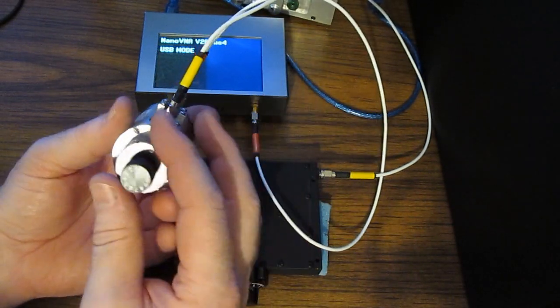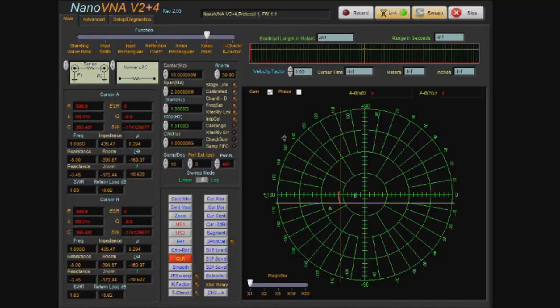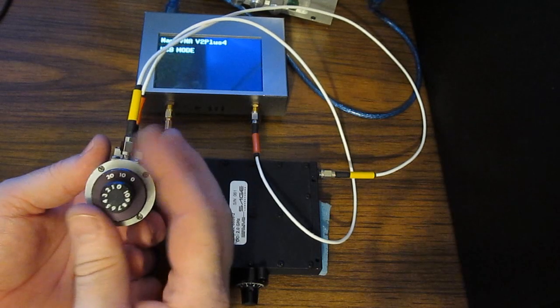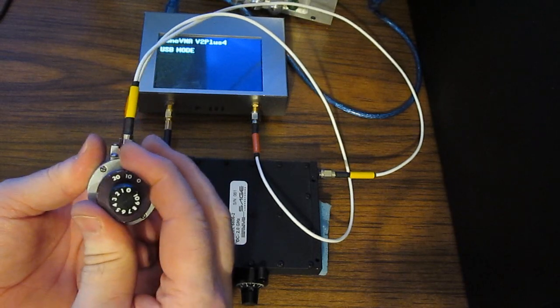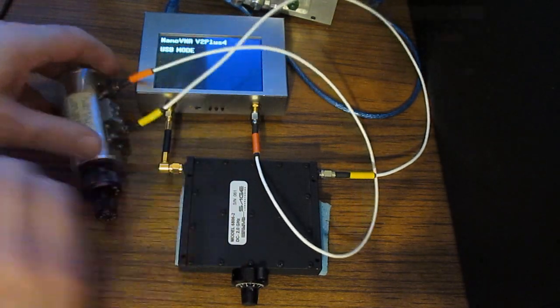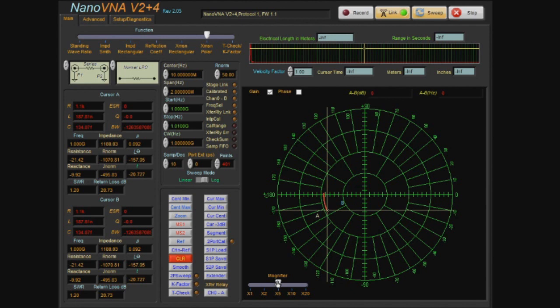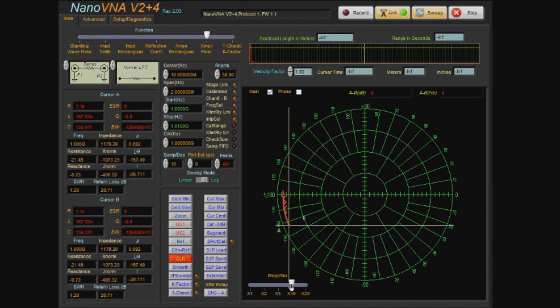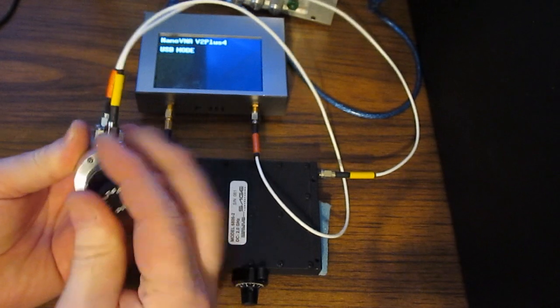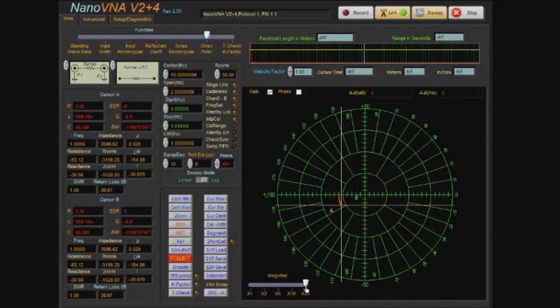Now let's change our step attenuator from 0 dB to 10 dB, and we can see how that moves our arc closer to the center of the display. I've added this magnifier feature. Let's increase this to 20 dB and change our magnifier to 5x, here it is at 10x.